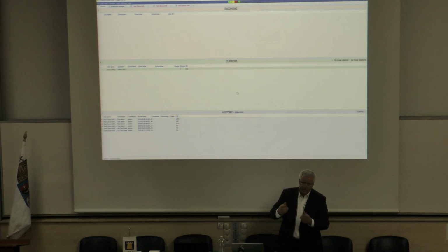Then the alarm drops down into my history queue, which is a database where we're keeping all those alarms in perpetuity. Those alarms are never deleted, and we keep the video with them, so the video is never deleted. Obviously, at your remote site the video is always overwriting, but once this alarm arrives in your alarm receiving center, all that video is kept on your central alarm gateway, and it's not lost. I can go back into any of these alarms at any stage and open it up, and it gives me a full history of that alarm: when it came in, when it was handled, and what information I've got with it. If I've had to fill out a procedure in an Excel spreadsheet, something like that, I'll send all that to that alarm.